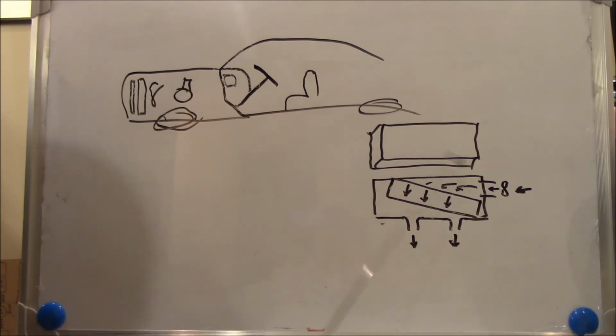But also, I haven't shown heat, but this same unit does heat. The way we do that, we sneak another heat exchanger in downstream of the evaporator, then run engine coolant, hot water, through it, and that's what heats it. So in the wintertime, none of this runs. Your compressor doesn't run, but the hot water goes into another heat exchanger to heat things up.